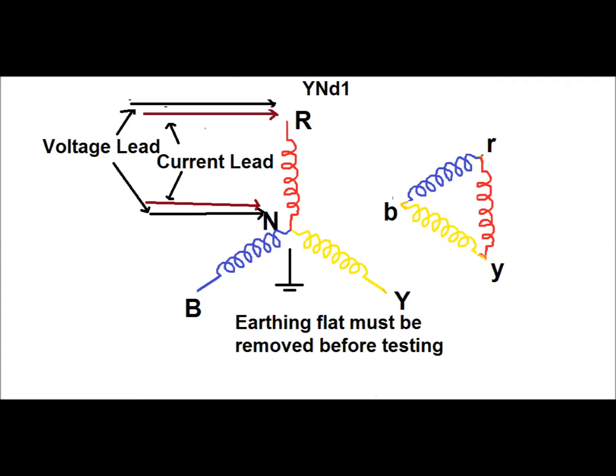Now, how the test arrangement is done for measurement of a power transformer with YND1 connection is shown in this diagram. First, the resistance test is done on the primary, or Y connected, winding. We have to remove the earthing flat from the neutral winding. Then we connect the voltage lead between the R phase lead and the neutral lead, and also connect two terminals for the current lead to the R phase lead and the neutral lead. Then we connect the other ends of the voltage and current leads to the potential input channel and current channel in the test kit.